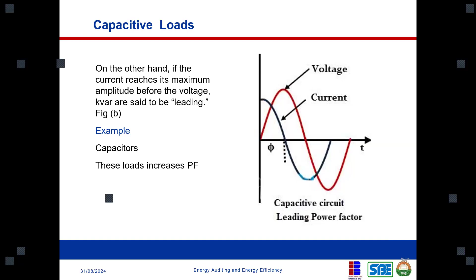This gives us an opportunity to actually correct the inductive lagging power factor. That's why, to correct a power factor, you need a capacitor bank to correct the power factor in a system. So we're going to see how you're able to calculate the amount of capacitor bank needed to correct any power factor in a system.